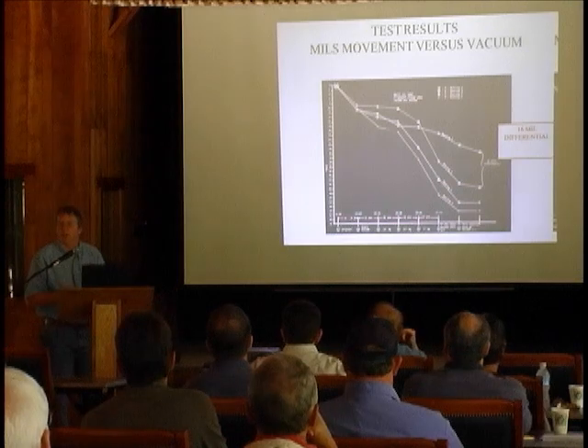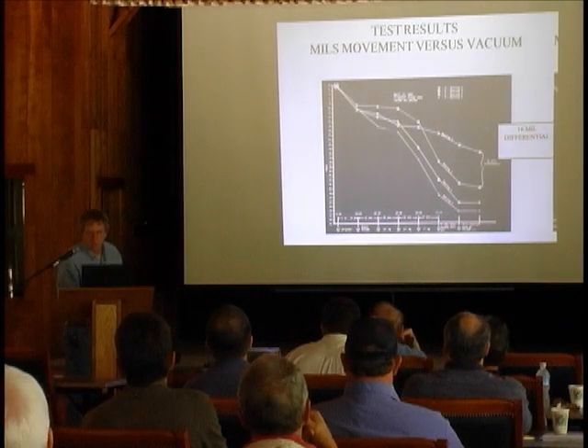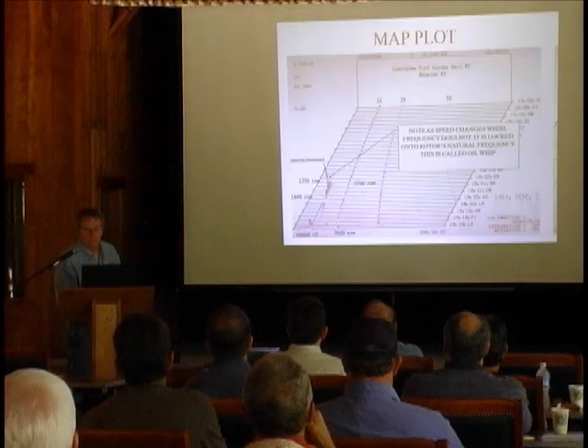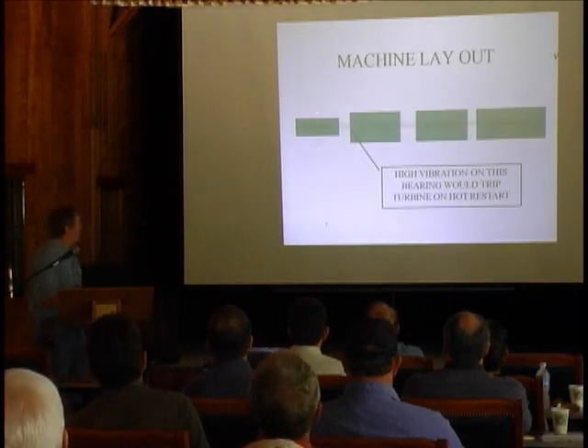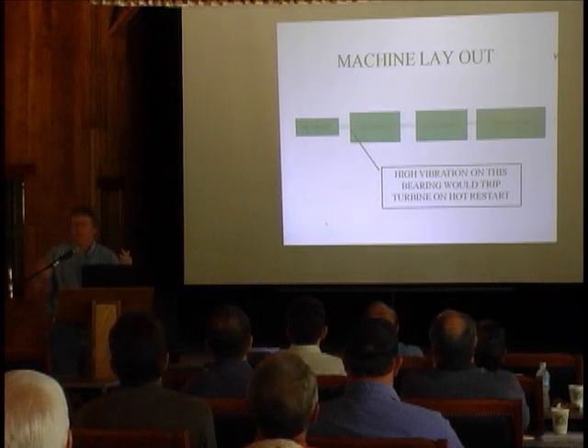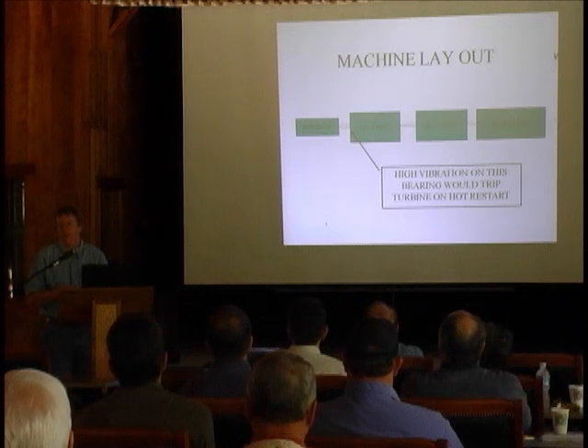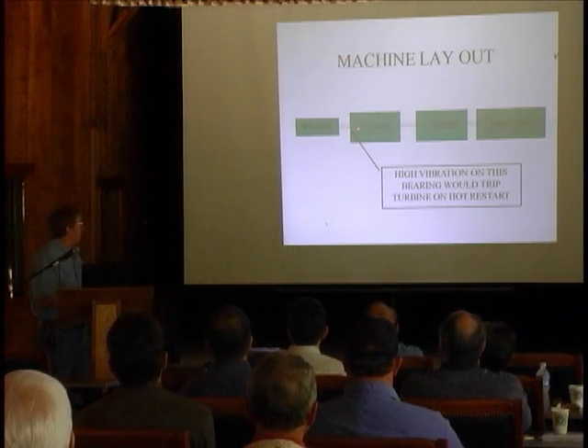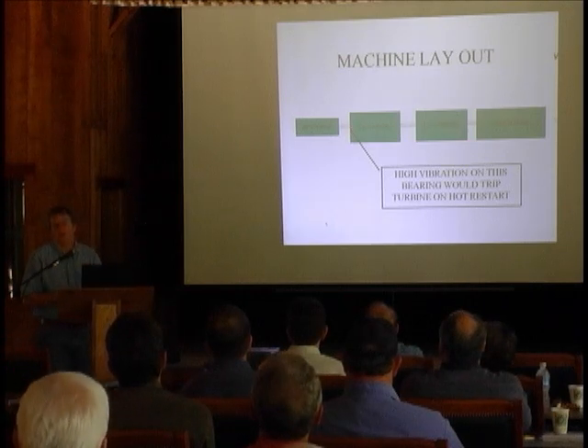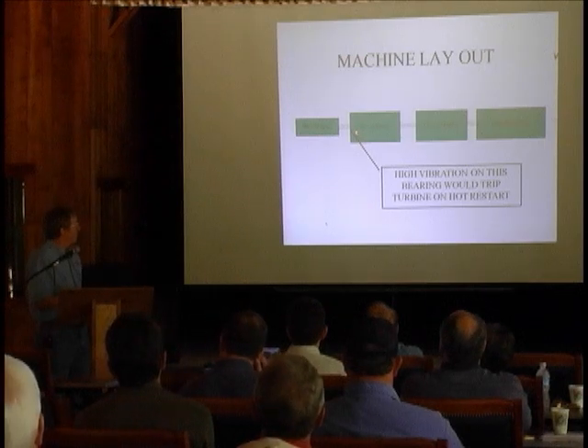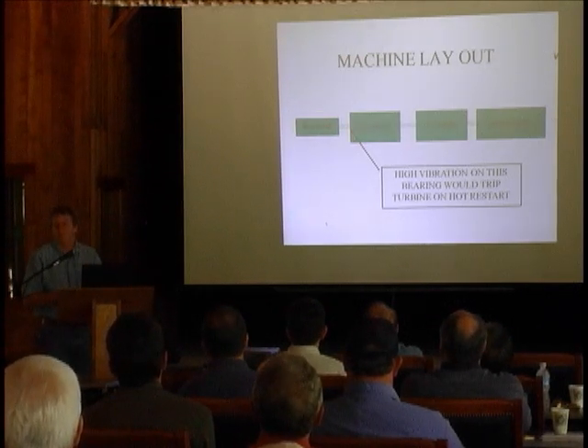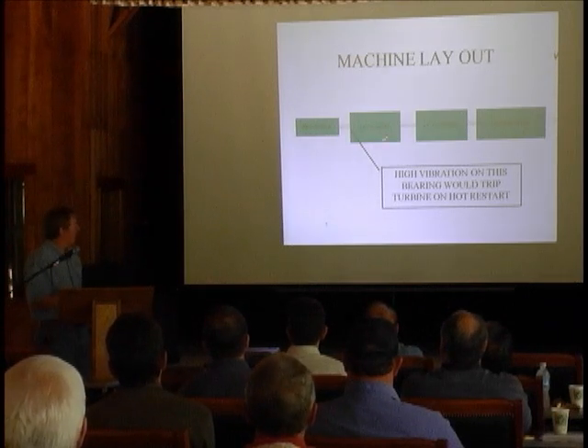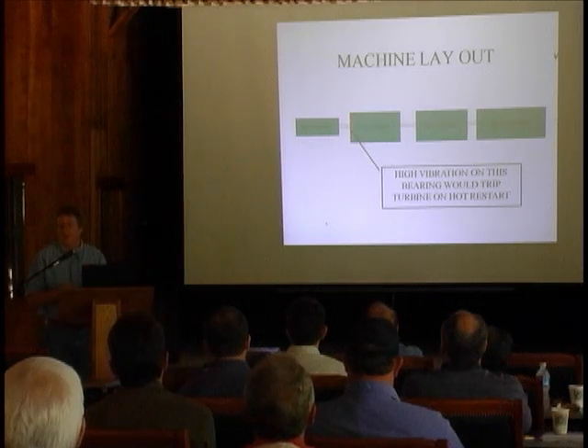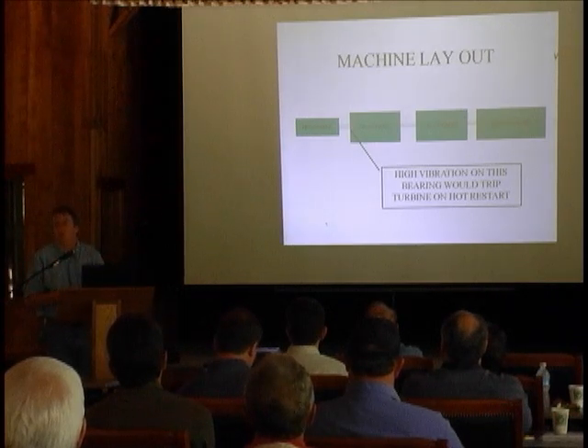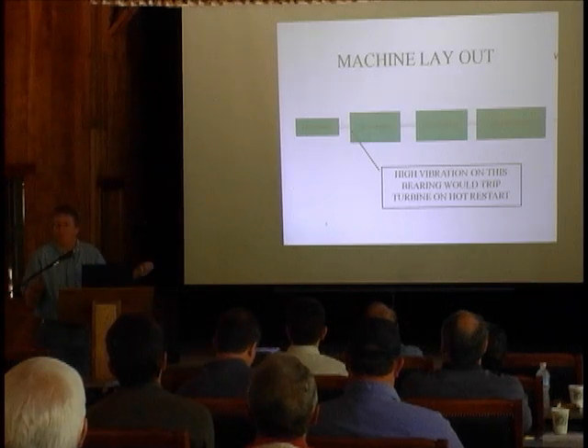So I said, yeah, but it does that every time. The key factor, though, was this is a big HP turbine. The steel is about this thick on it, 2,400 PSI. It's a hunk. This is a low-pressure turbine, thin shell wall. So what happens when you shut it down is this cools down much more rapidly than this. So we have two factors. Then we have the condenser drawdown, which is lowering this bearing. Then if you shut it off, in a 2 or 3 hour period, this one drops significantly. That gets enough misalignment going to whirl. If you wait 2 days, both of them get cool.